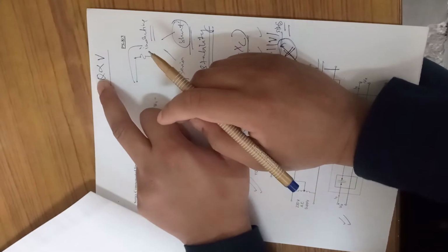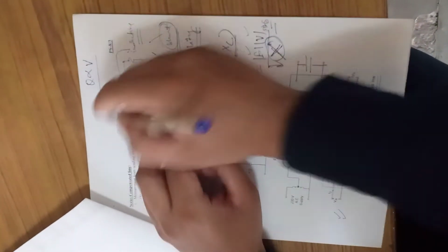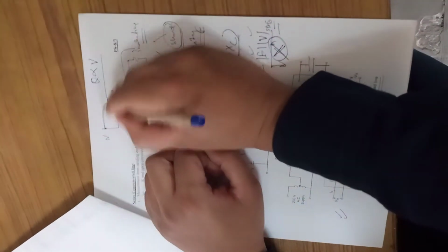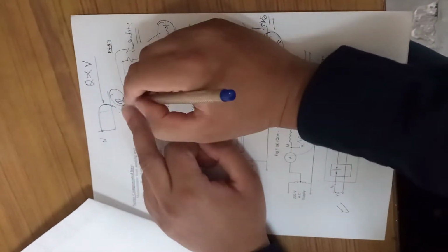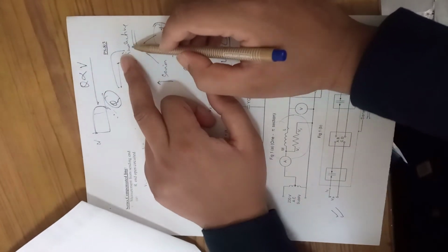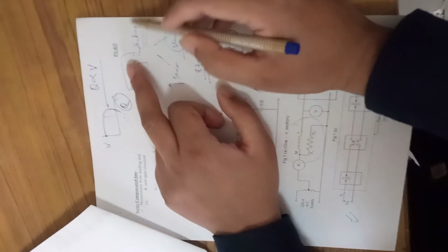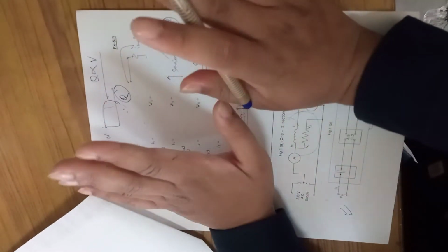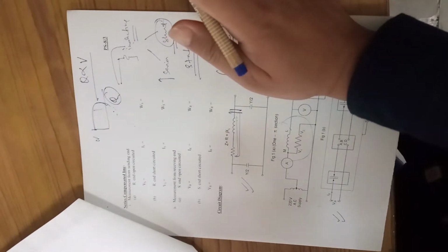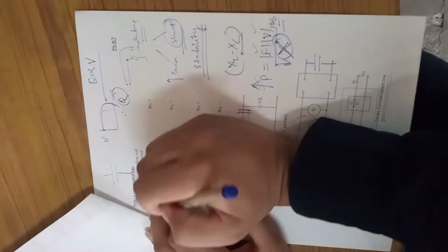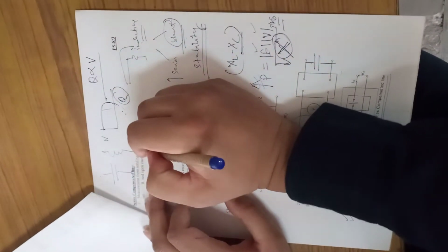If there is a deficit of Q in the system, voltage collapse will happen. That means the voltage will go down. Okay, just like this. If the Q deficit keeps on increasing, the voltage will after a certain point collapse. That means the lagging VARs which are required in the system by the inductive load, because most of our loads are inductive, fans, motors, transformers, whatever load you take is highly inductive. Now to compensate that load, you need capacitor banks. That capacitor bank can supply those lagging VARs to the system, or you can say the capacitor supplies plus Q to the system. Basically, capacitor is the source of reactive power, inductor is the sink of reactive power. So this balance needs to happen at every time in the system.